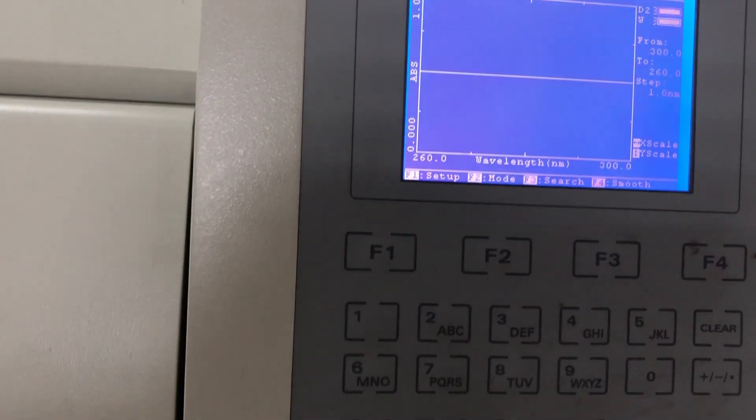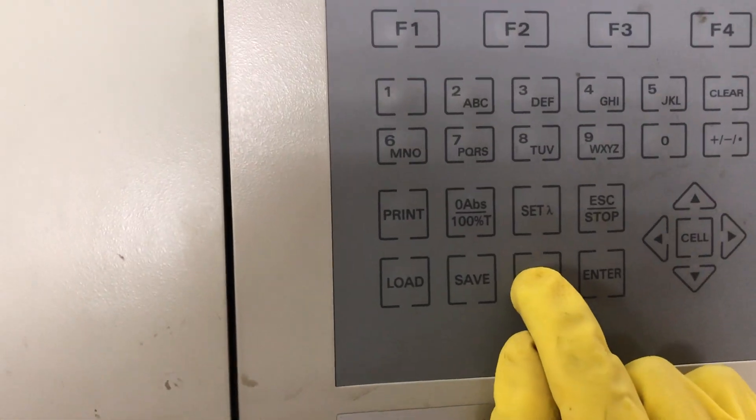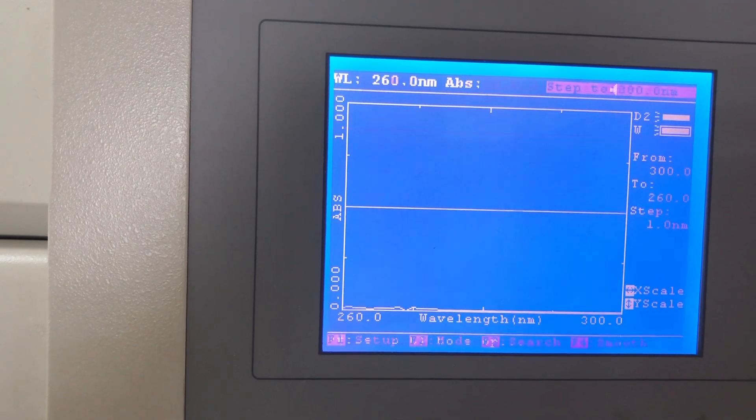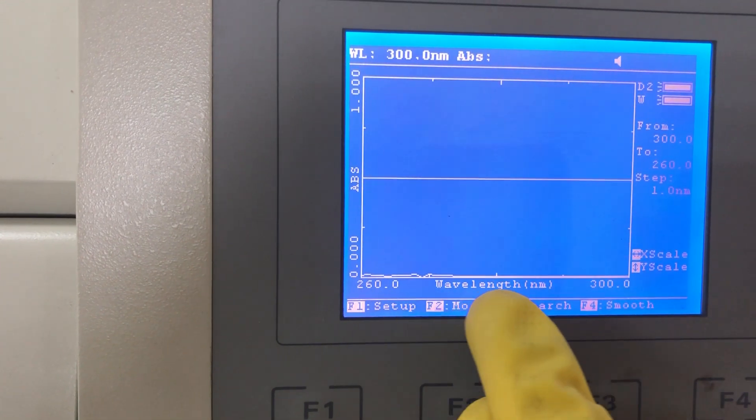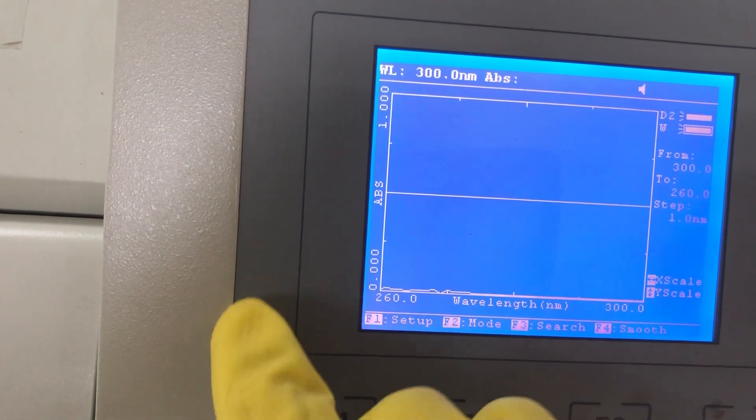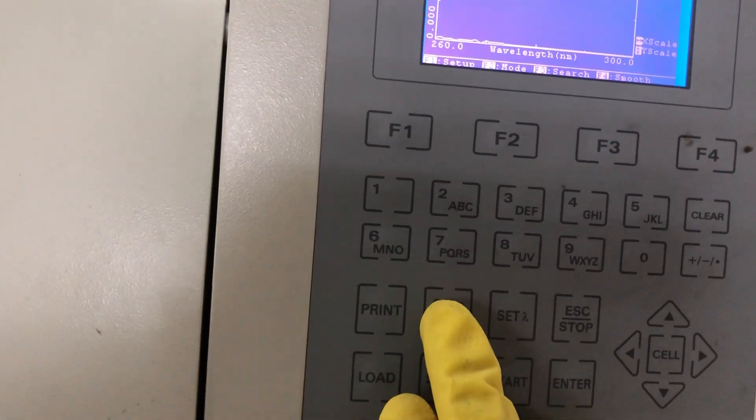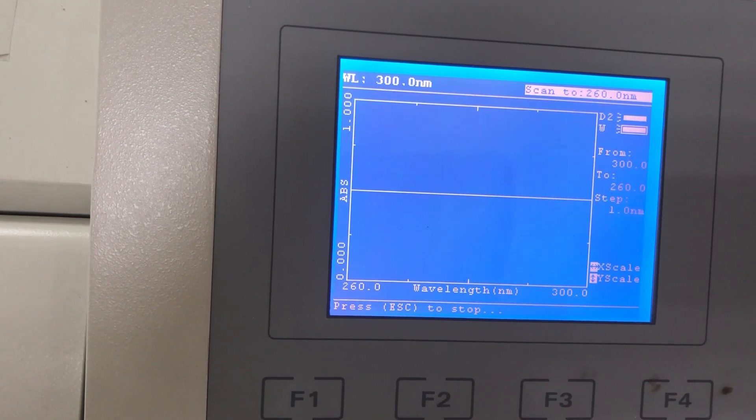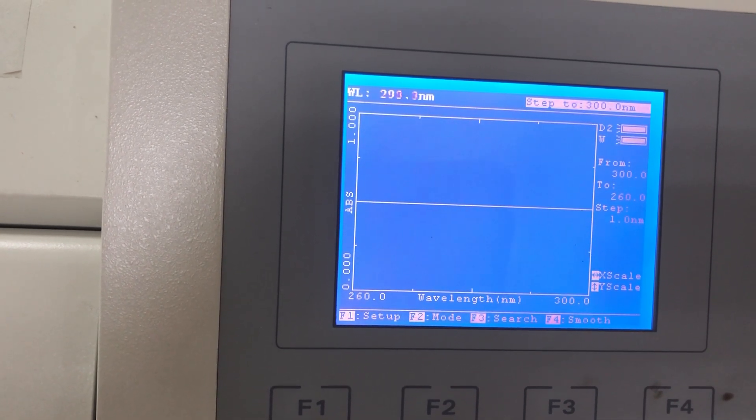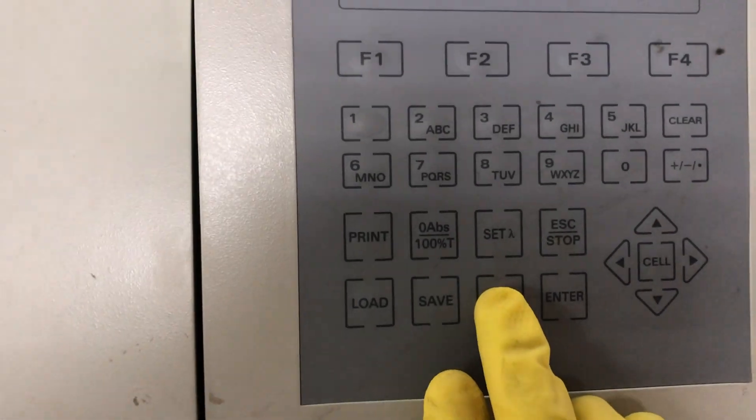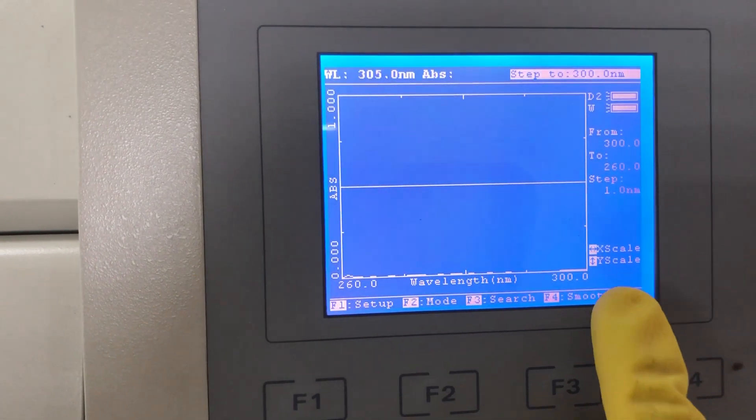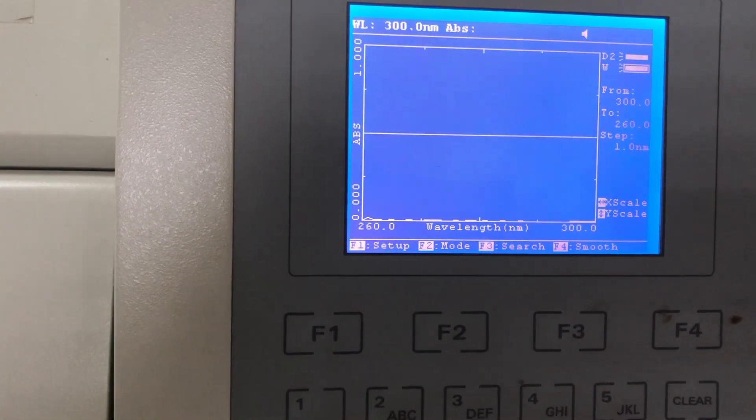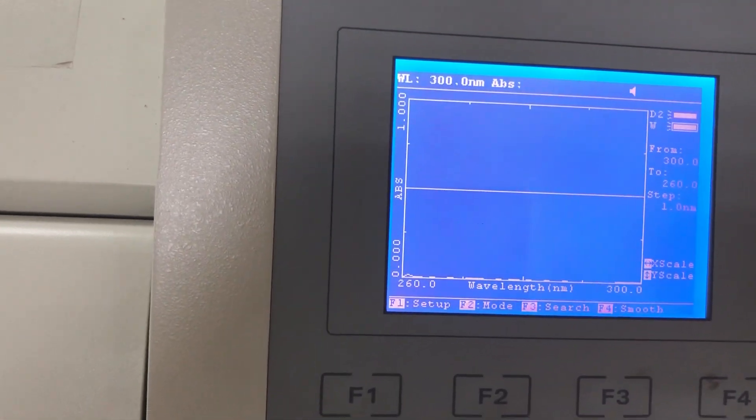You can just start to scan the blank sample. See here you have some small noise in the scan. Once again, press zero zero, and then press start to scan the blank. Almost zero. After the scan is finished, you will hear beep sound three times.